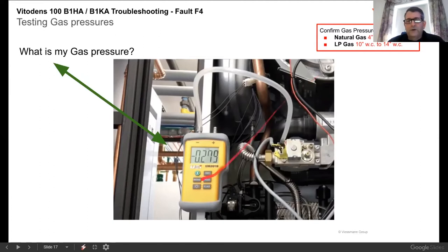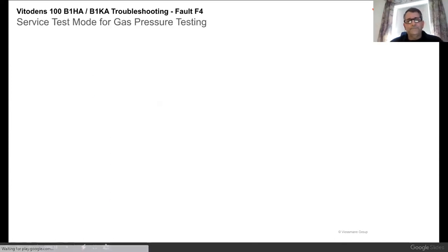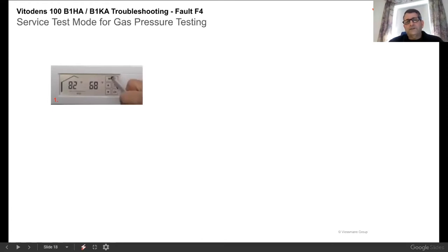As you can see, my hose is now hooked up to the gas valve. Where that slides onto, there's a small flat tip screwdriver. You're gonna just crack that open and leave that open. So when you wanna do your high and low fire test to do your combustion test when you first install it, there's no need to take that off. Once you put it on, you're gonna be fine. And then you're gonna go through the controls and we're gonna go over all of that as well. So this is how we're gonna test our gas pressures.